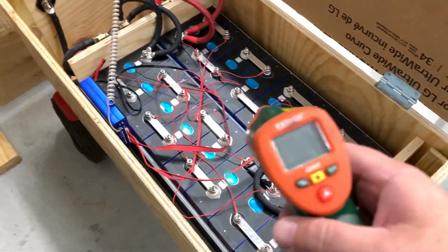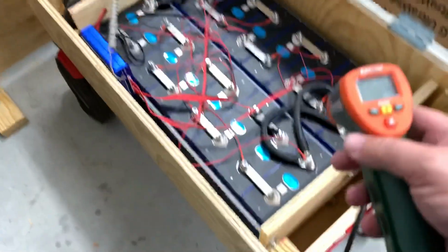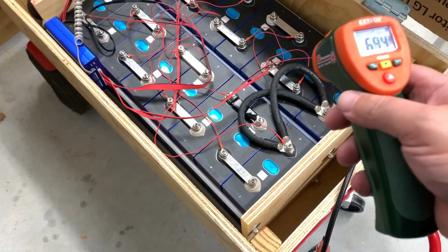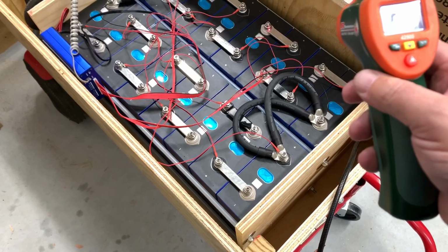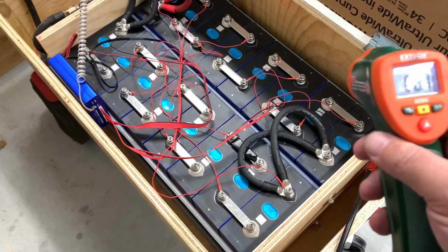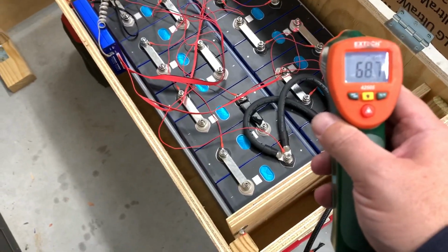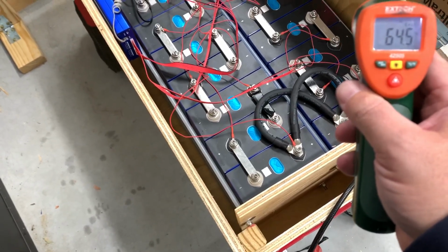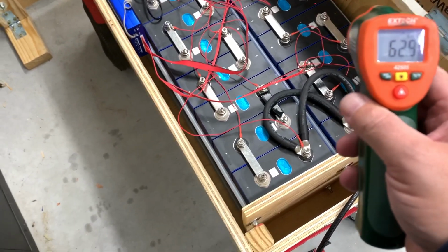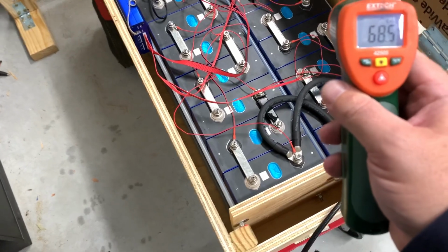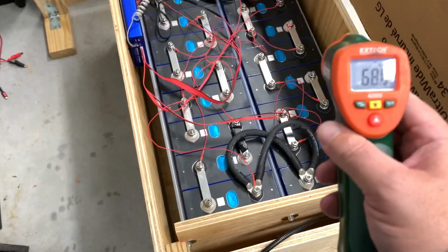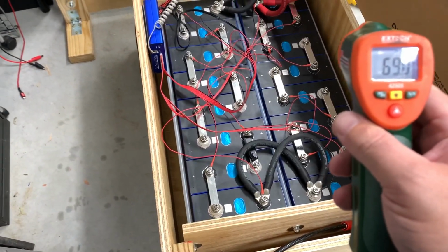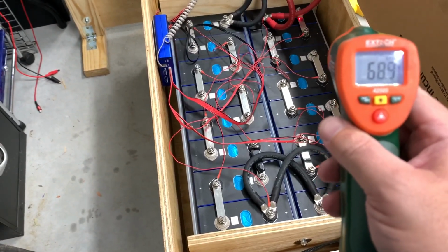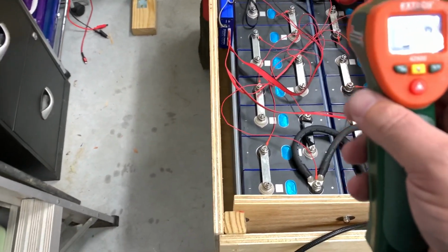But anyway, this is a handy tool for measuring actual temperature. You can see the little red dot here, and I'm reading 68 degrees. If I point it at the wood, it's 63 degrees. So I don't have any significant temperature rise occurring even when pumping 85 amps into the battery bank. That's obviously good, so I'll keep cranking that up and keep checking for problems.